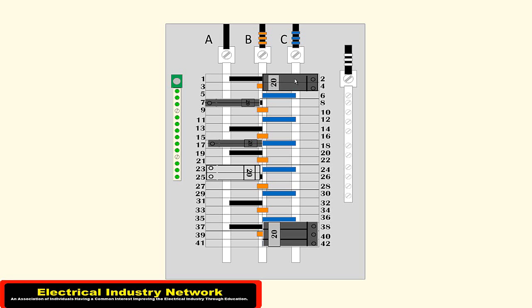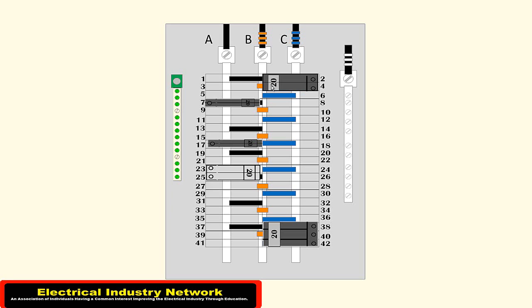you got to watch this because if for some reason you have circuit 2 and 4 and a neutral going out to a piece of equipment, you may have circuit 4 feeding something 110 in your piece of equipment. If that's the case, you definitely don't want that on the 208 leg because you're going to fry something. So make sure that when you're using that middle leg, that high leg, that it's running straight on equipment only.